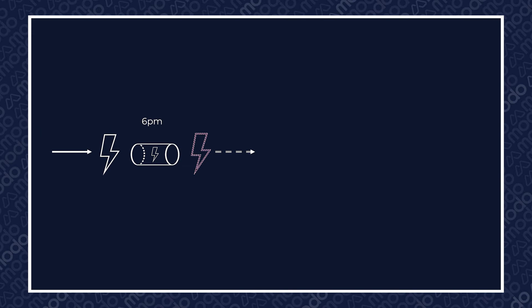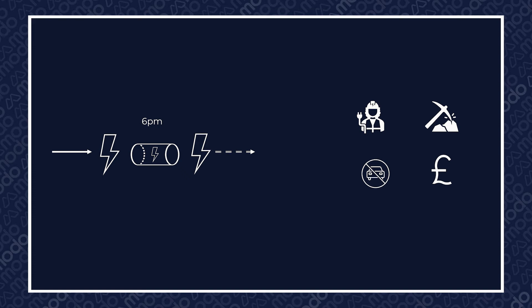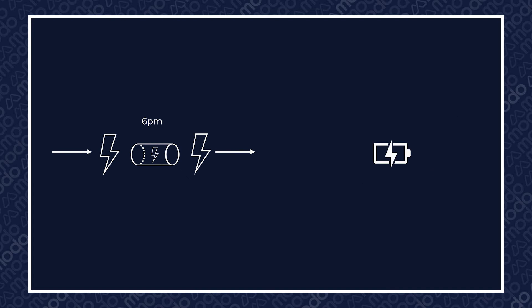To stop the peak demand exceeding the available capacity, a source of local flexibility can be dispatched to reduce the peak demand to 750 megawatts — in this case it's a battery which charges up when demand is low, overnight. By calling on a local source of flexibility to shift energy consumption away from peak times, network power constraints are respected, which means no transformers going bang. This also means costly and inconvenient network reinforcements aren't necessary, so nobody has to start digging up your local high street.